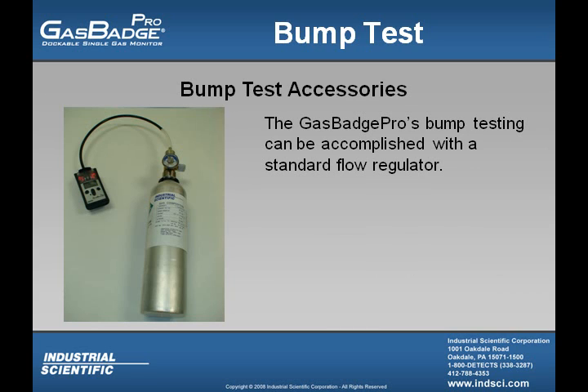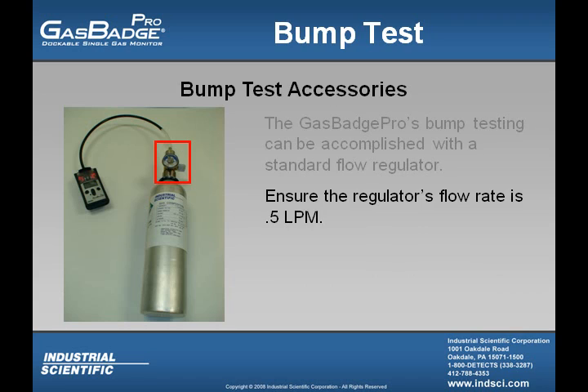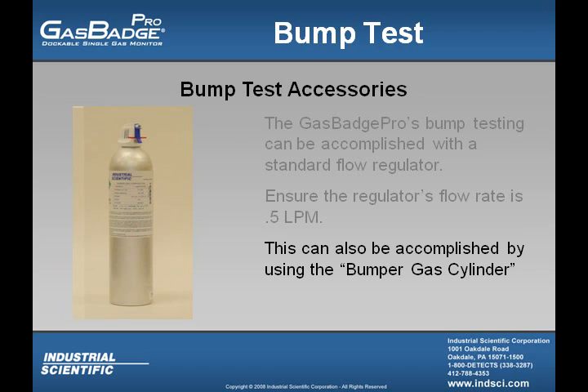To perform a bump test, the user must have a standard flow regulator. The user will also want to ensure that the regulator they are using has a flow rate of 0.5 liters per minute. The bump test can also be performed using a bumper gas cylinder, which is an aerosol-based bottle where the user would just simply press the trigger and wave the gas along the top of the sensor.